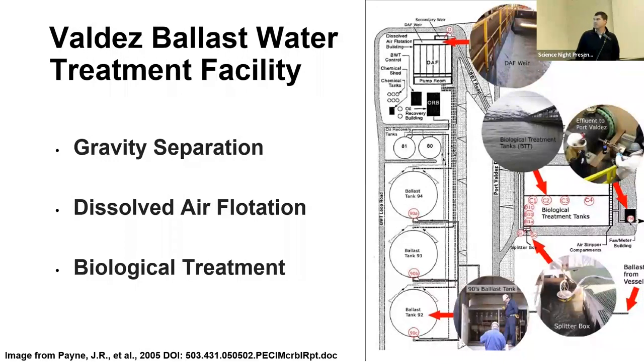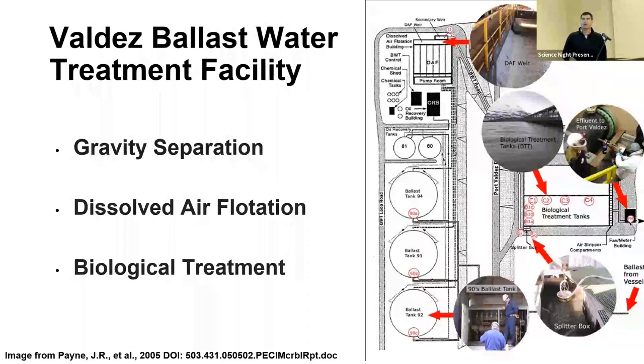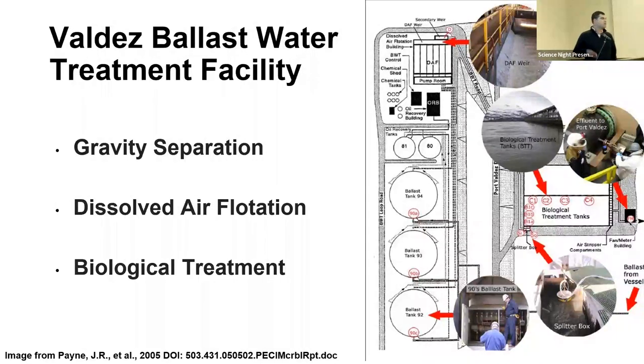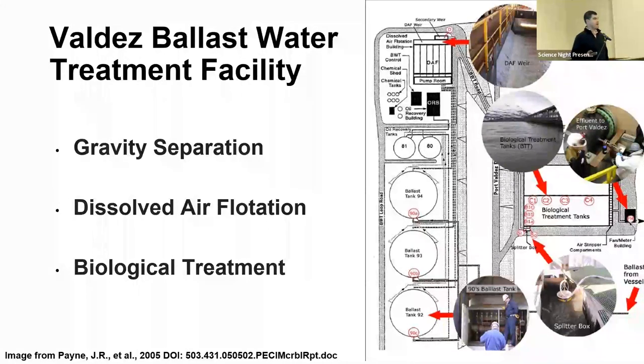The Valdez ballast water treatment facility uses gravity separation — the oil floats to the top, you skim it off, and send the rest to a DAF (dissolved air flotation), where you bubble air through it to get rid of volatiles like BTEX. The final and most interesting step for us is the biological treatment step, which is supposed to take the remaining hydrocarbons and degrade them into compounds that are no longer BTEX or total petroleum hydrocarbons. These are oxygenated analogs — some hydrocarbons are degraded and released as gas from the microbes, while others are just transformed into these leftover products.